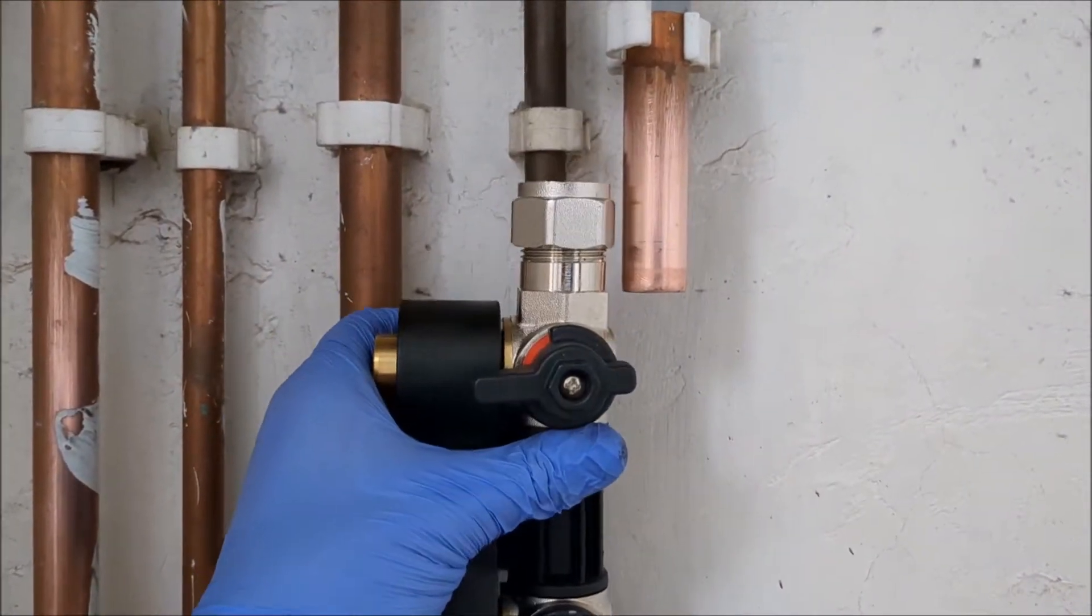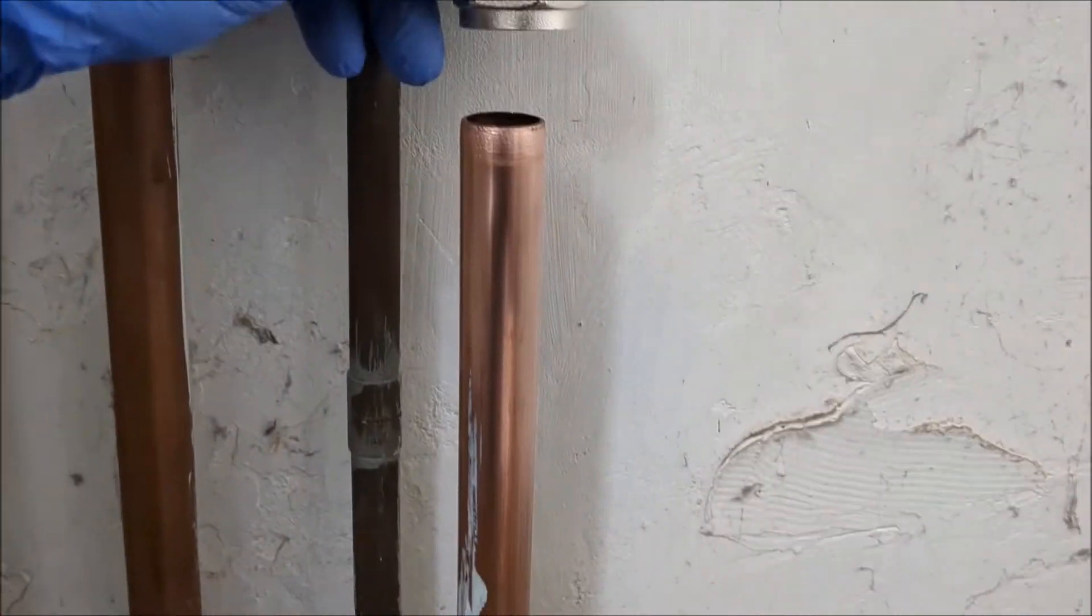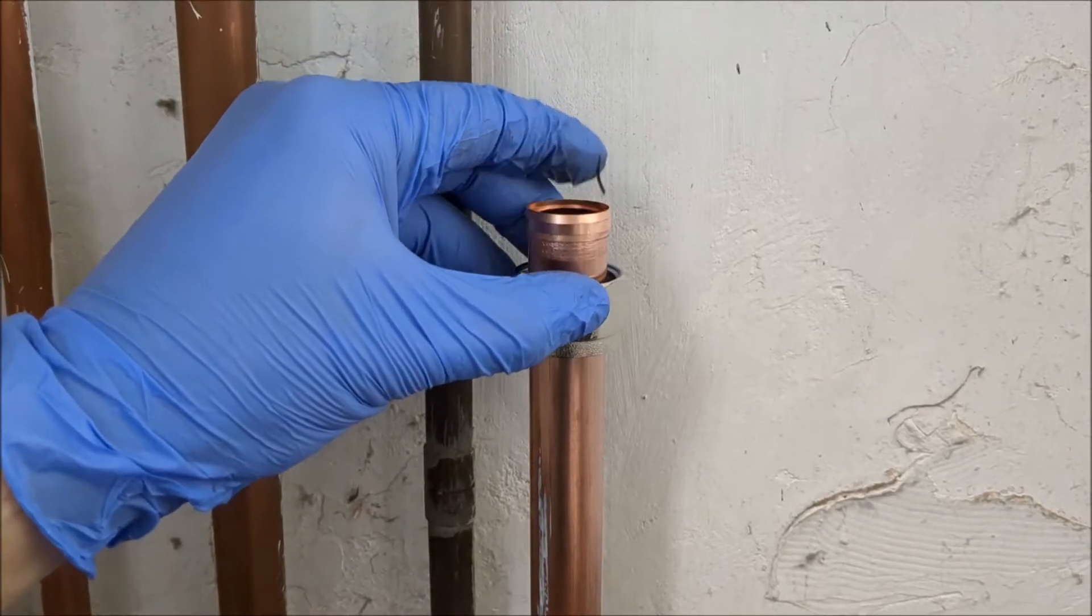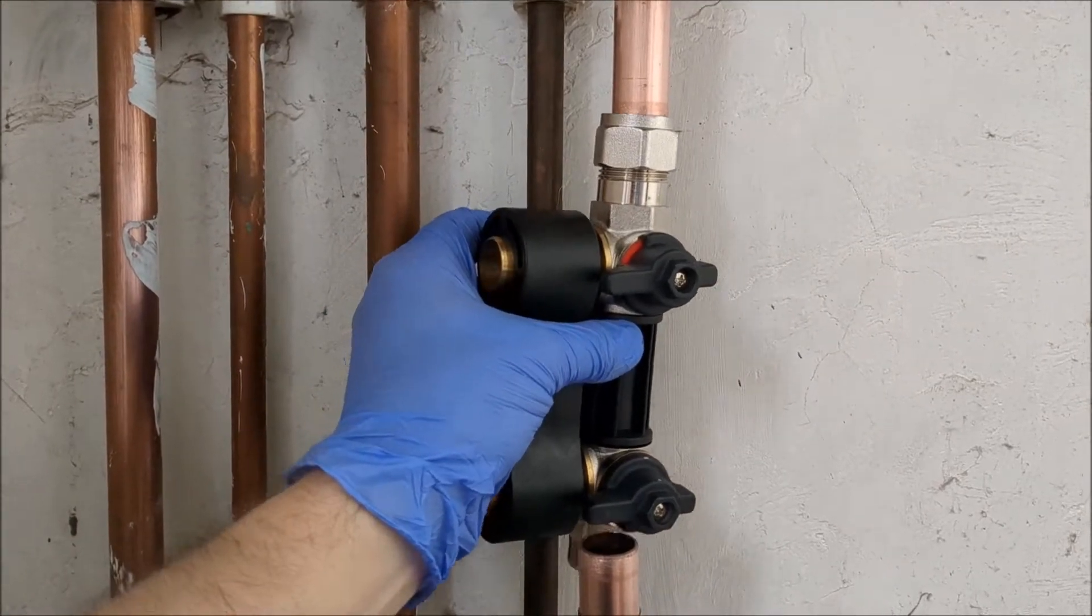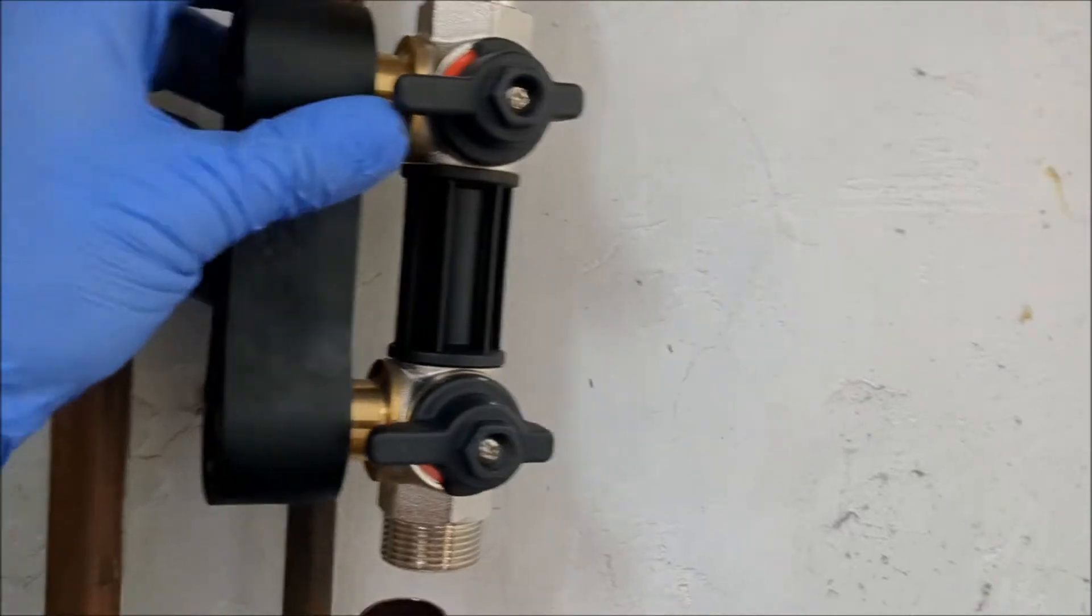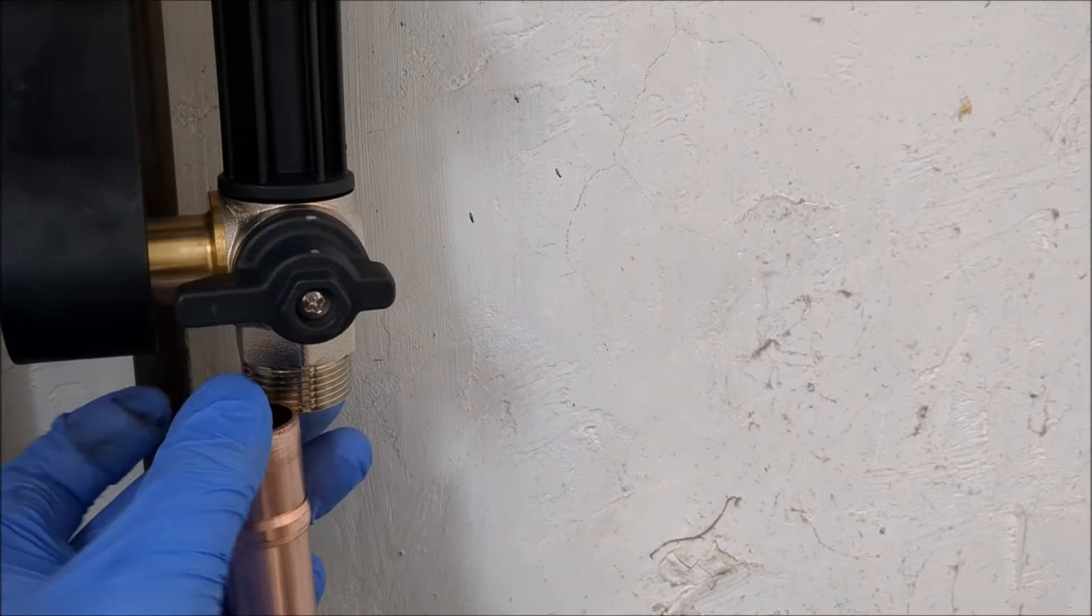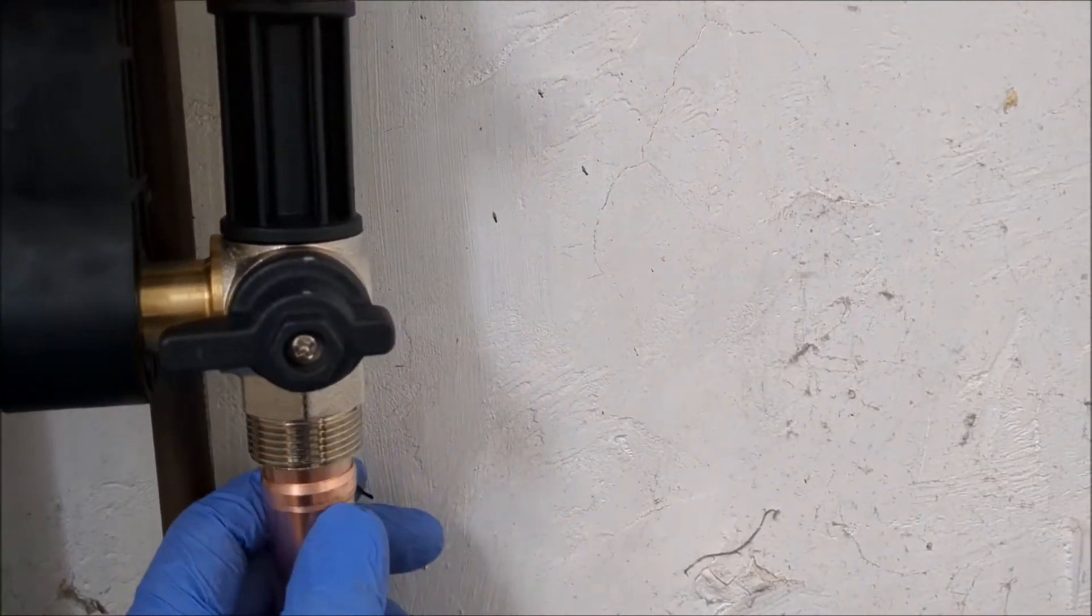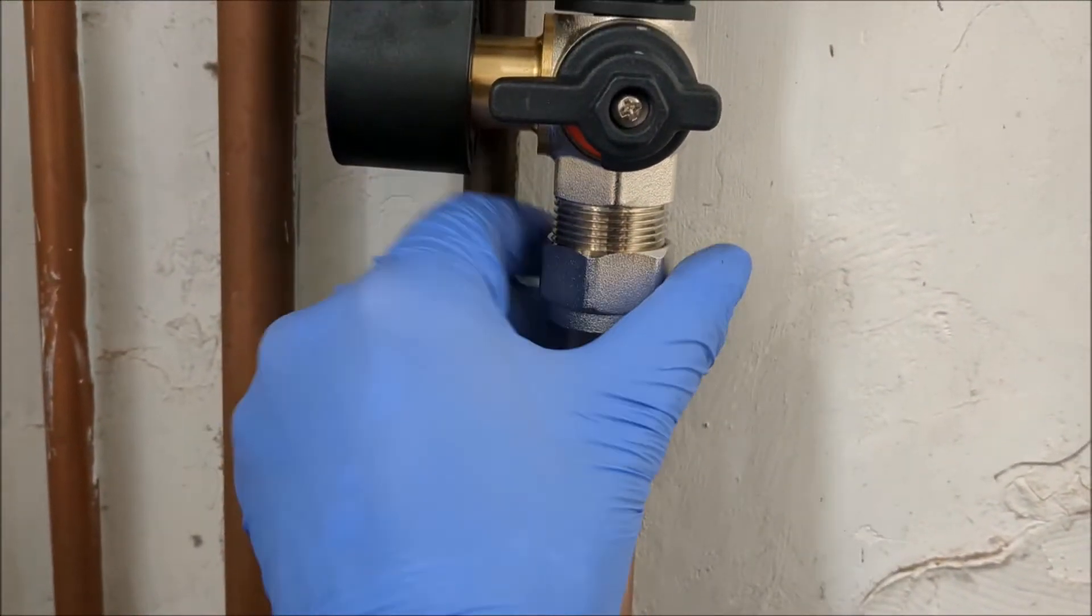Remove the nut and olive from the lower MagnaClean isolation valve B and put them on the lower pipe. Slide the valve assembly onto the upper pipe with isolation valve A on top, then slide down onto the lower pipe until it stops. Slide up and reattach the nut to valve B.